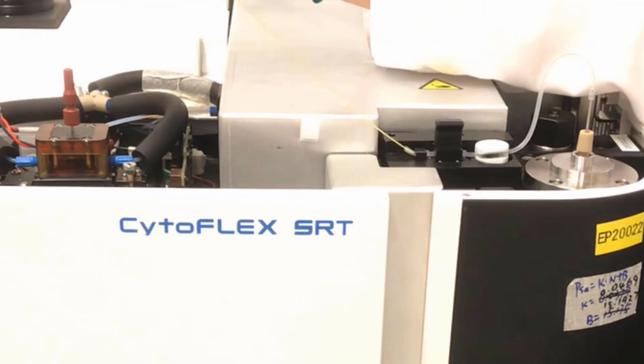Every time you replace the sample line or remove the silicone tubing from the sensor, you will need to calibrate the sample line bubble detector. This can be completed by all users and doesn't require service to complete it. Refer to Chapter 11, Calibrating the Sample Line Bubble Detector, to complete this procedure.